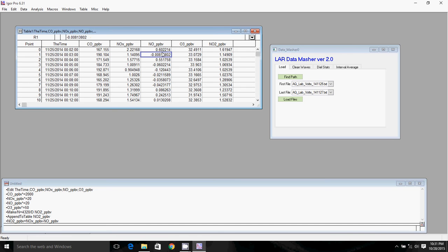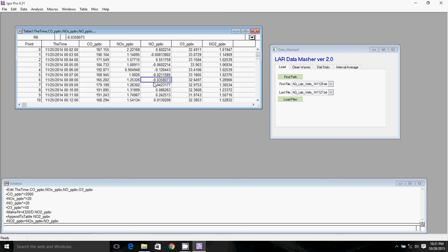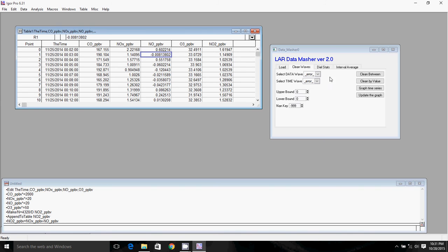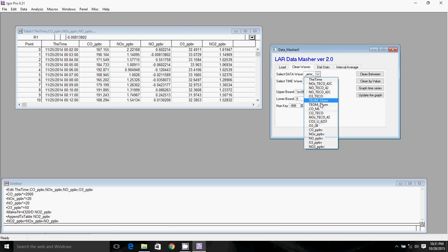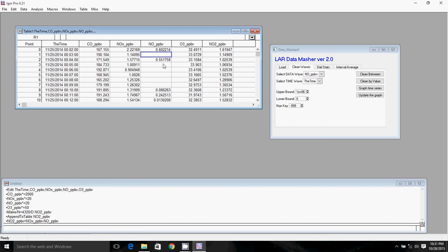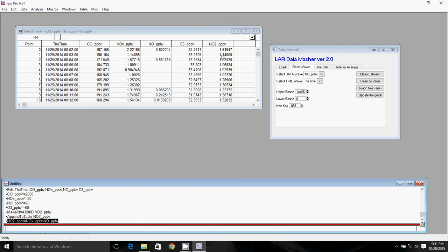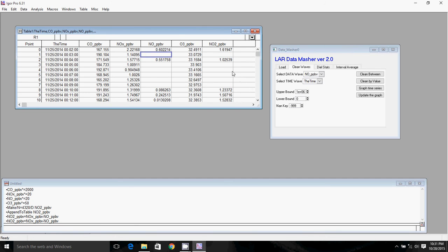One thing to note here is we have negative values in our NO wave, which, as you might guess, is physically impossible. So what we need to do is use our data masher to clean out all of these negative values. So the way we do that is we go to our clean waves tab in the data masher. We set an upper bound that's really high. I mean, if you wanted to clean out high values, you could do that. But then we set a low bound of zero. We'll select NO as our data wave. We'll select the time as our time wave. And then we'll just go ahead and click clean by value. And you can see all of those negative numbers fall right out. Now we'll go ahead and recalculate NO2 because we have some erroneous NO2 values, because NO2 can't be higher than NOx. So we're going to go ahead and recalculate NO2 and thereby take out all of the NO2 values that are higher than NOx.